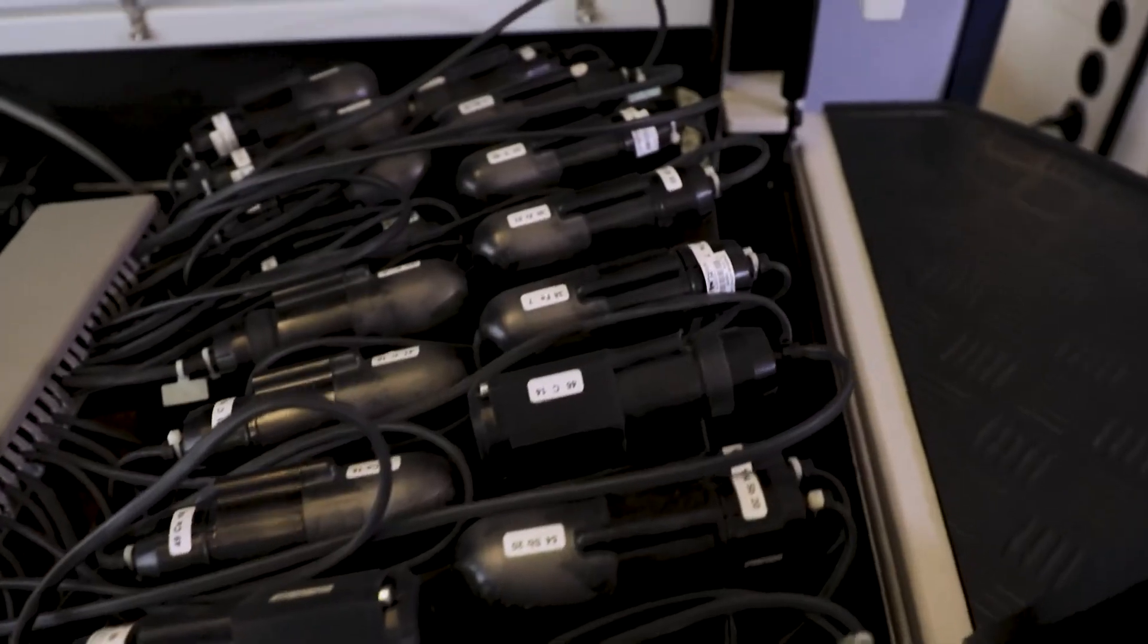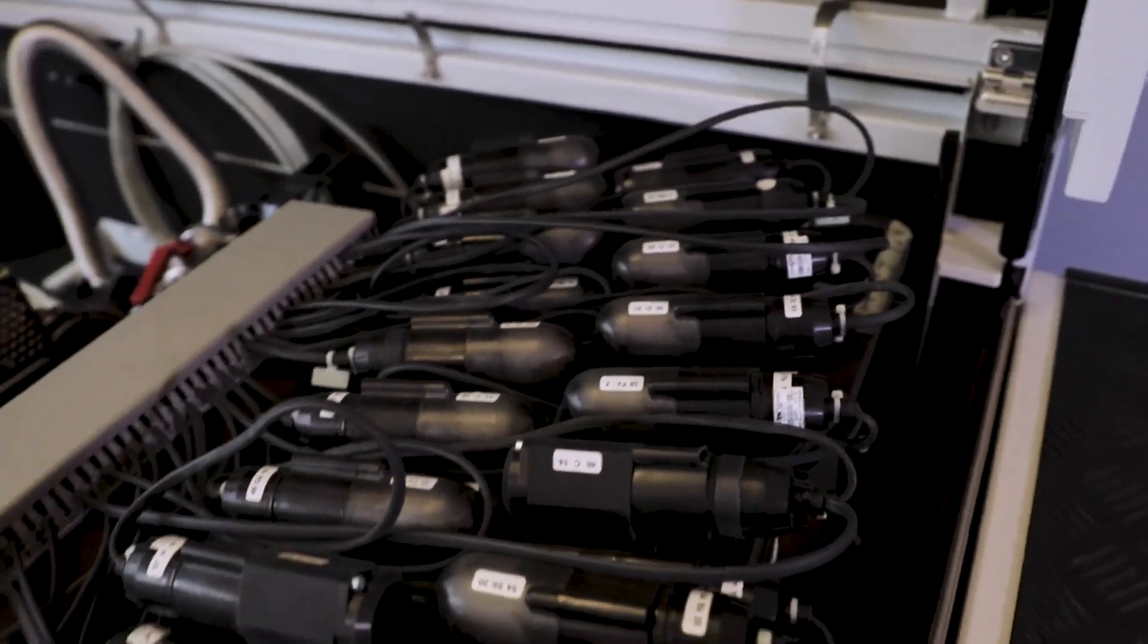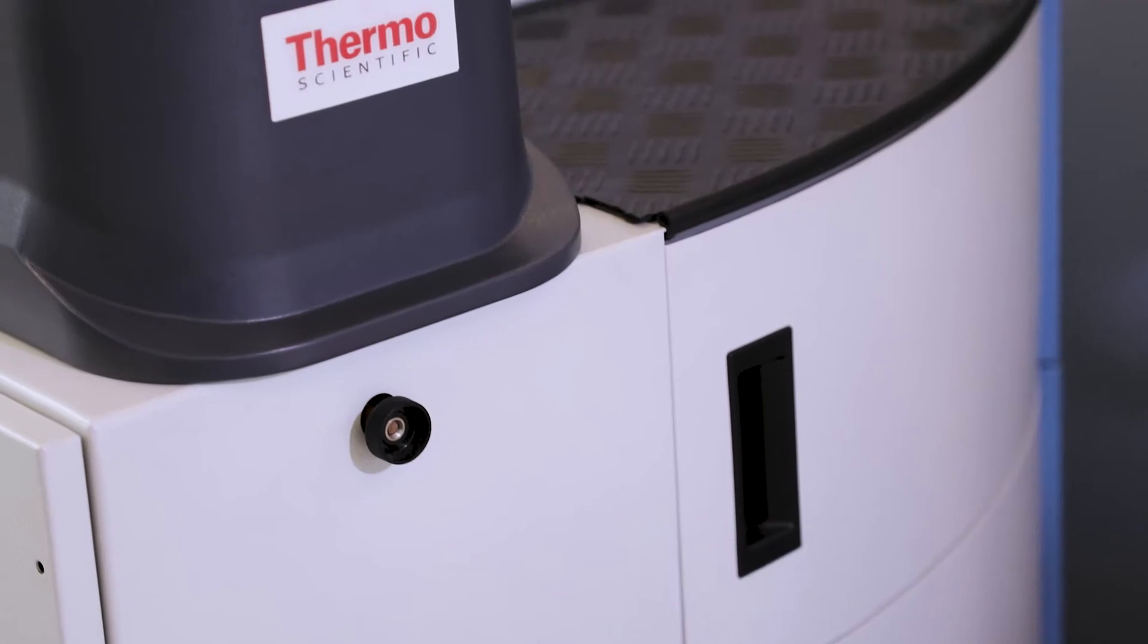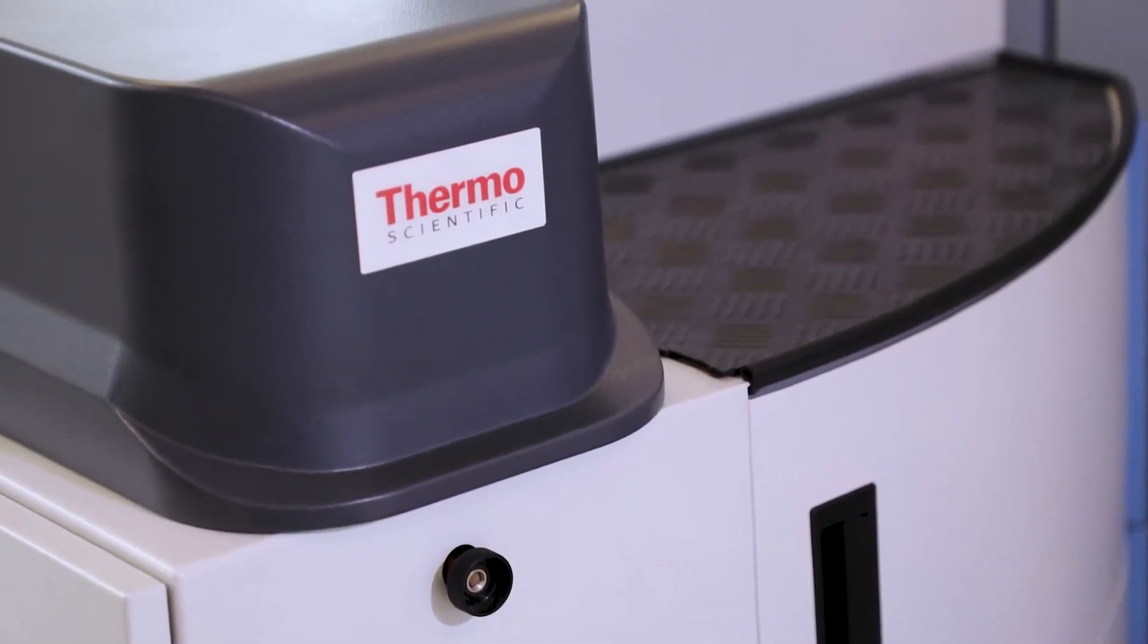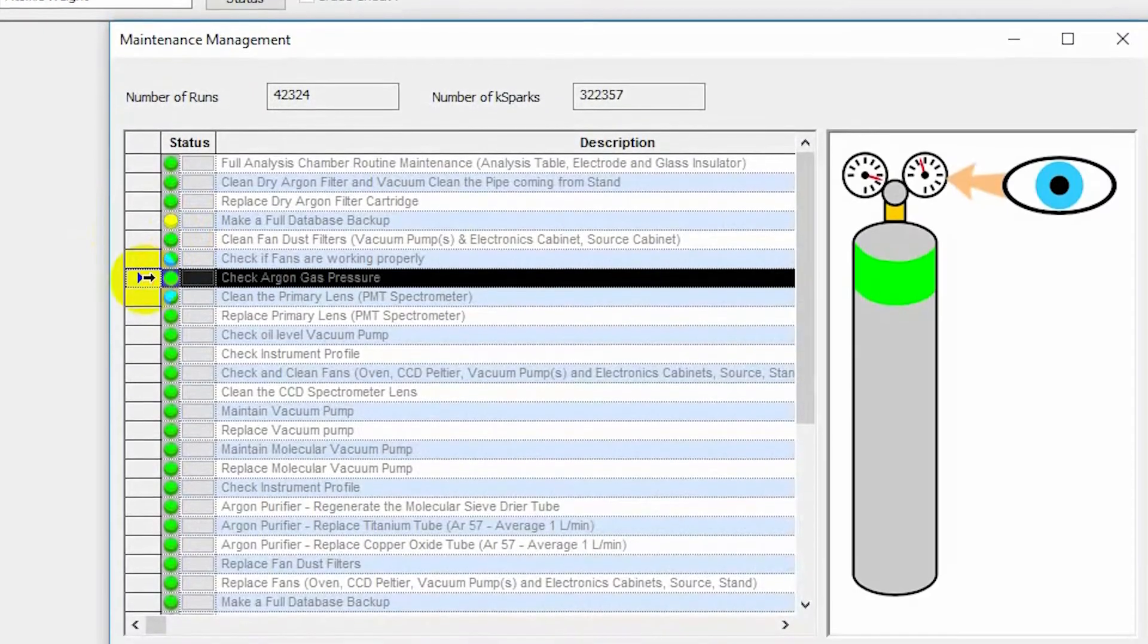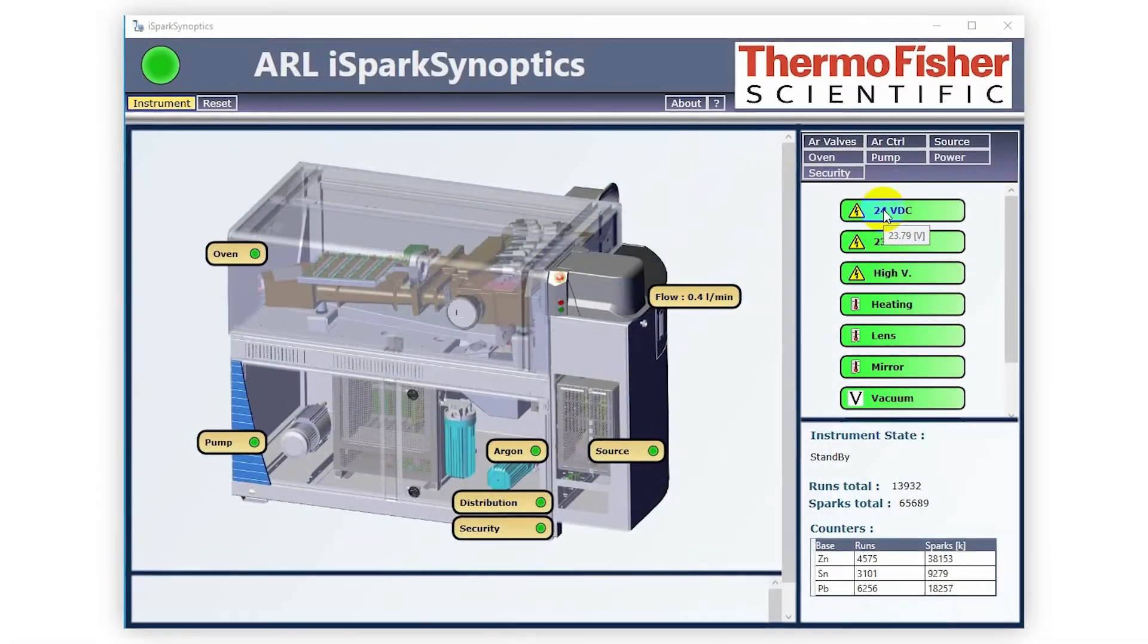The main modules of the spectrometer have been newly designed, leading to improved instrument performance, reliability, and ease of use, as well as a reduction in maintenance and argon consumption, thanks to an innovative, computer-controlled argon circuit design.